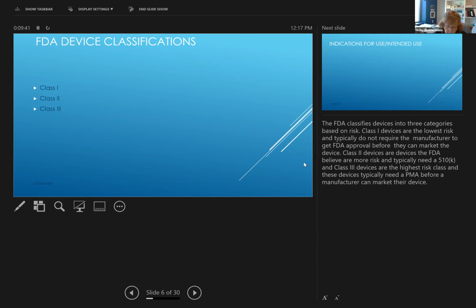Gary, can you say generally whether an improvement or a new class 1 device that has minimal risk, is there any FDA submission that has to be made in those types of cases? There is not, as long as that change does not change the risk class. So if you're still a class 1 device, you can still make that change. You document that in your files, basically your design history file, but no, you do not need to submit that to the FDA. As long as you stay within your class and you're not changing things, they would move that device to a higher risk class.